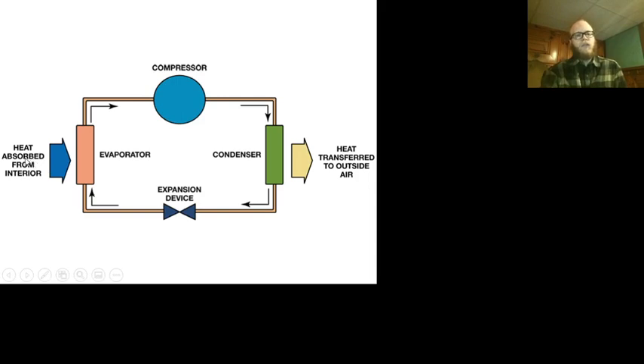He also noticed if you draw a line through the evaporator and the condenser, you can see what side has vapor. Vapor comes out of the evaporator, vapor goes into the condenser. You can also see what side has liquid. Liquid leaves the condenser and enters the evaporator. So by just drawing that cross, basically, you can tell what state of matter the refrigerant should be and what pressure it should be anywhere in the system.